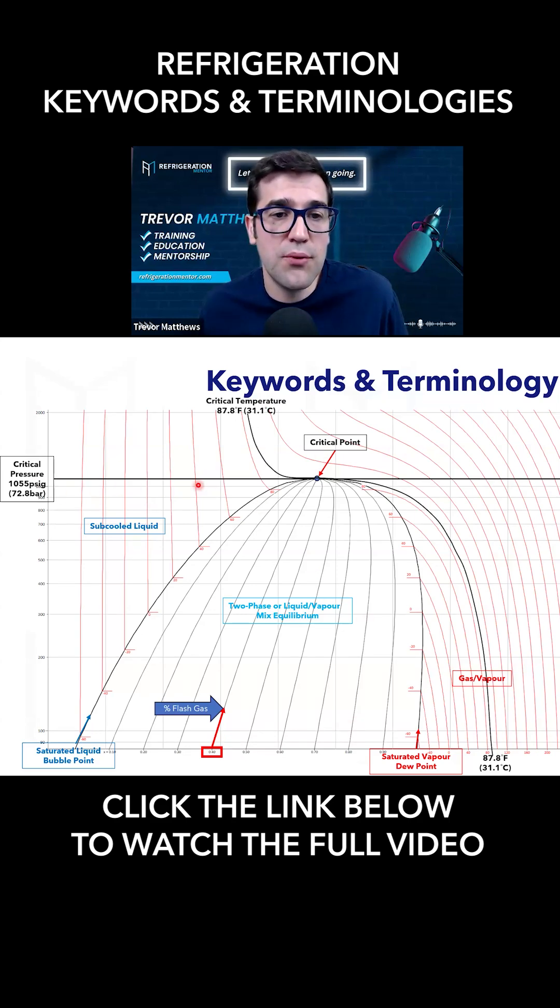But we also have a critical pressure line. So you need to be above both of these. When you're above both of these, that's when you are in supercritical or your system's in transcritical. If you're not above both the critical pressure and critical temperature, you're not going to be in supercritical.